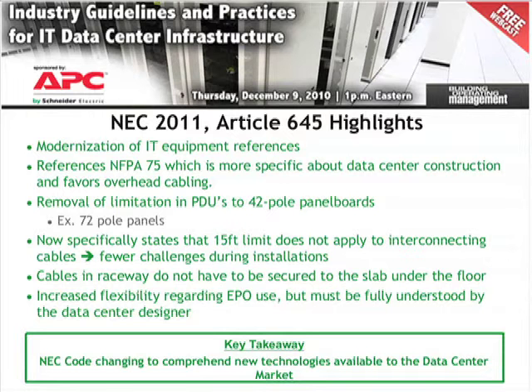Okay. Just to give you some other highlights that are in here, things like the number of poles in a PDU. I think many folks can relate to the idea of having a PDU or a panel board that's full of breakers, and somebody rolls in 3 more racks, and I'm already using all of the poles in my panel. I need to go get 5 more poles. I'd love to be able to put in a bigger power panel, like a 72-pole power panel, but according to NEC, I can't do that because it's against code.